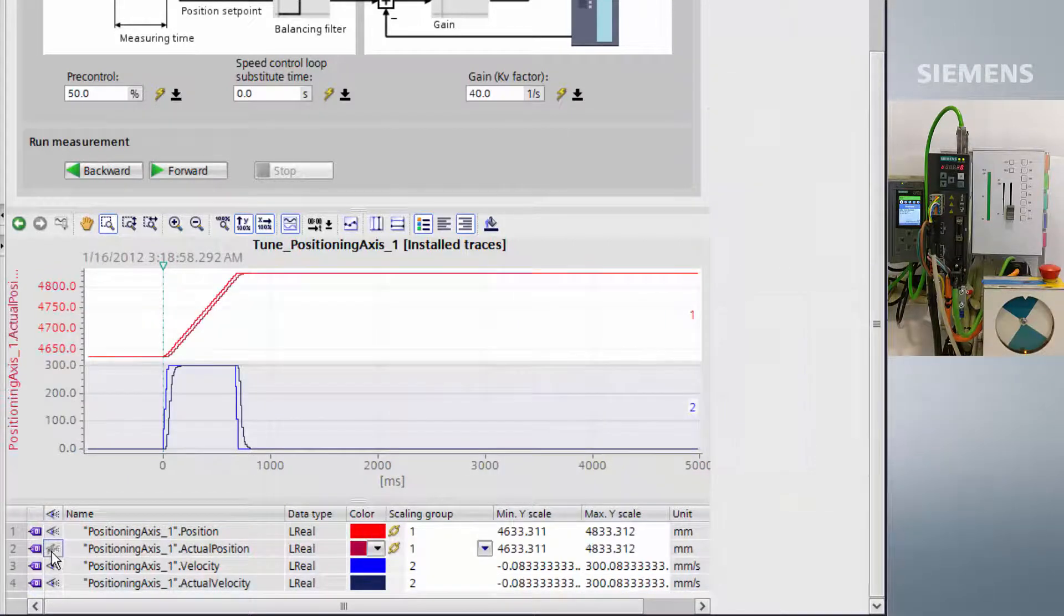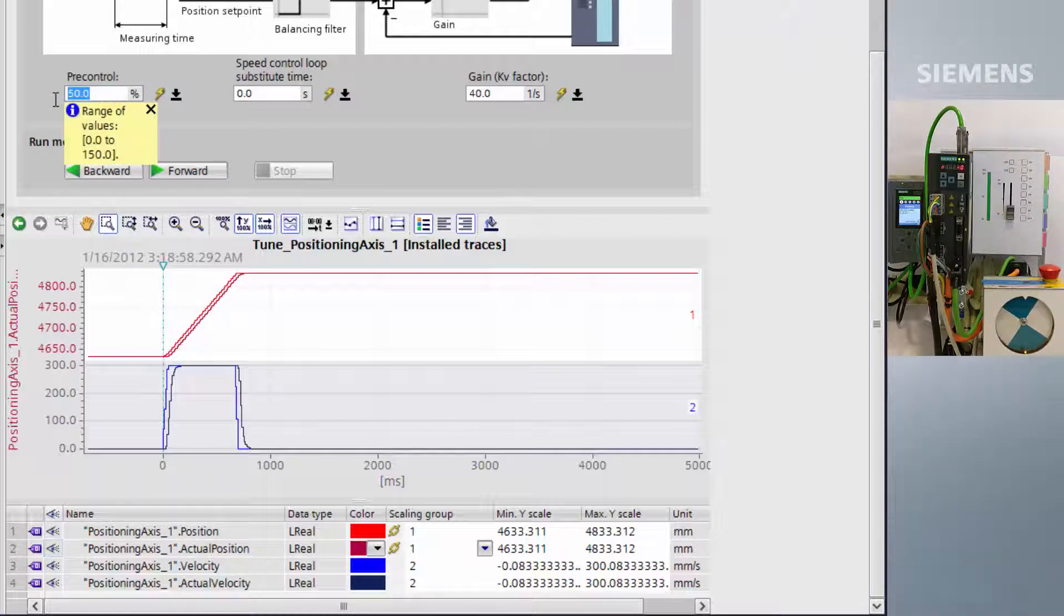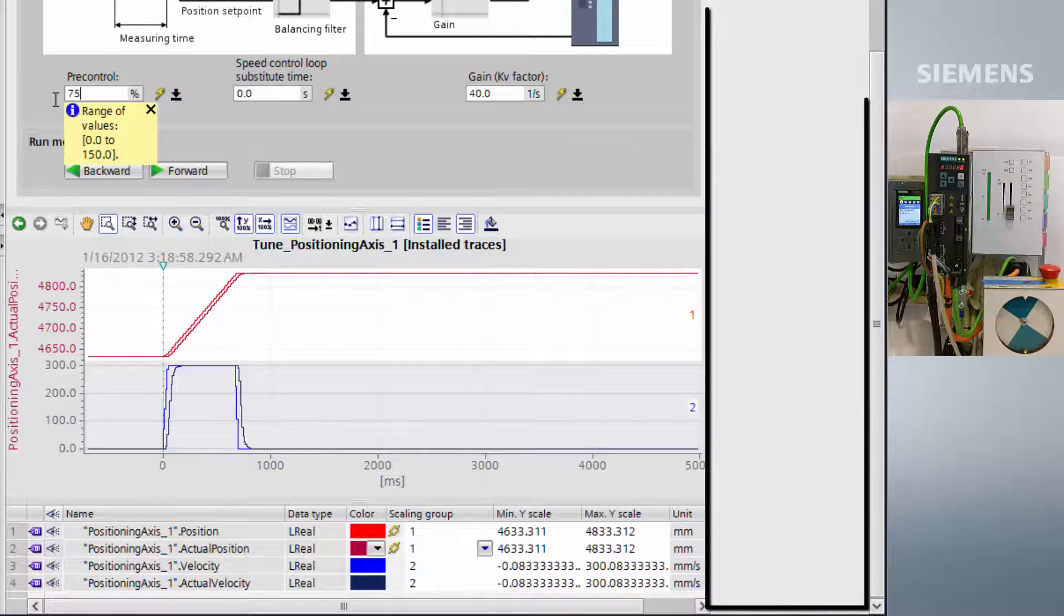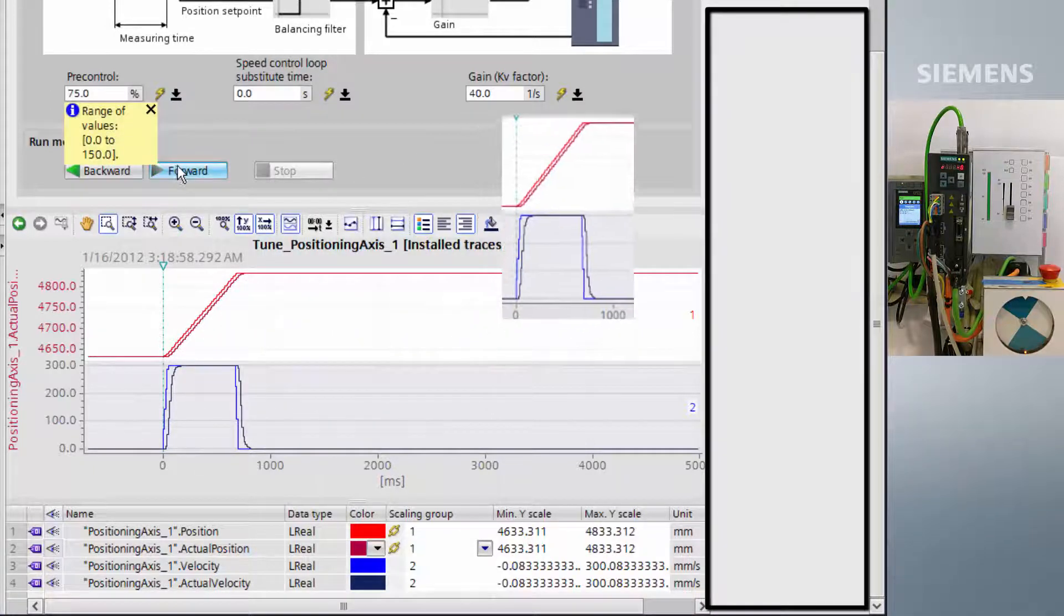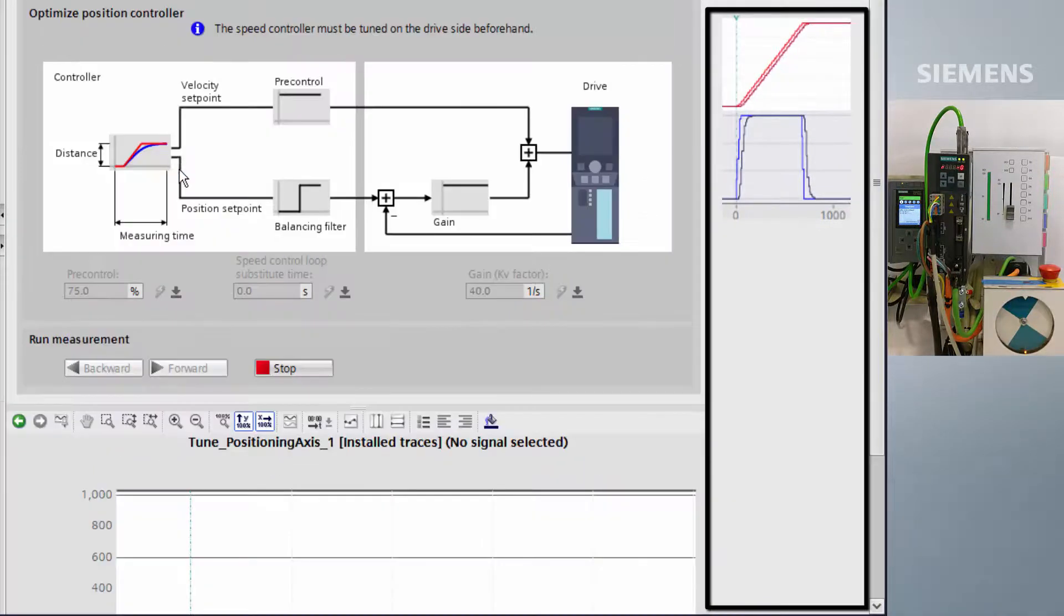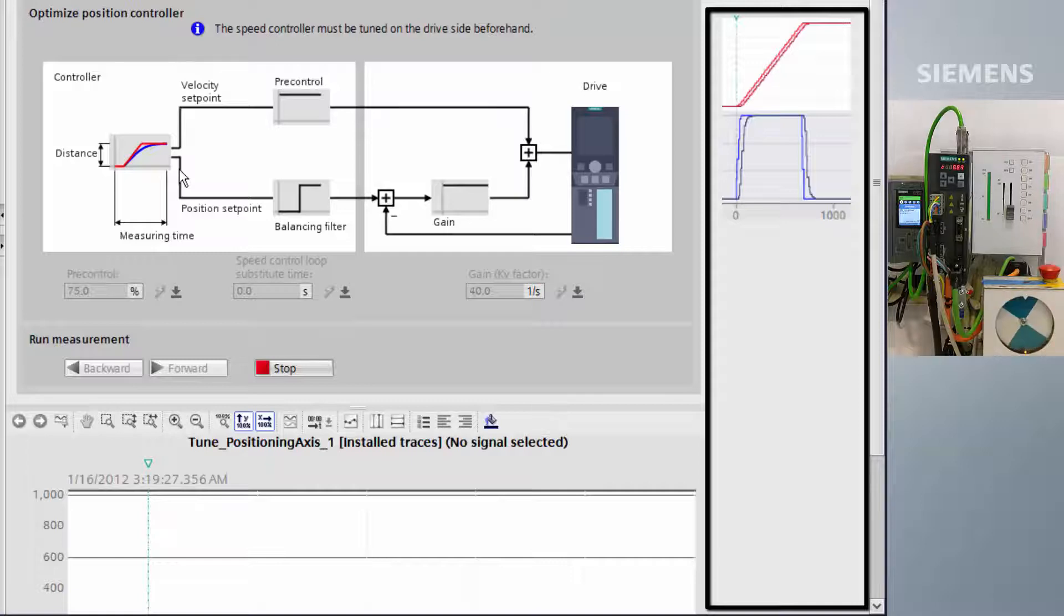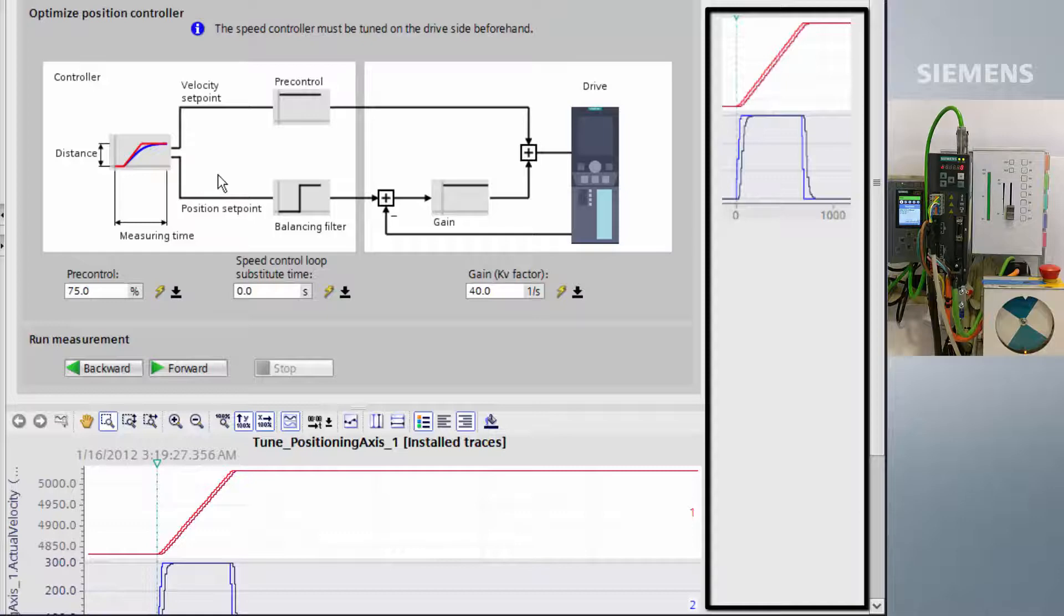Pre-control is defined as a percentage of the speed setpoint which can be fed forward from the interpolator. As this application has a very low inertia motor and very little load on the end of the motor, we can increase pre-control all the way up to 100% and get a very dynamic response.